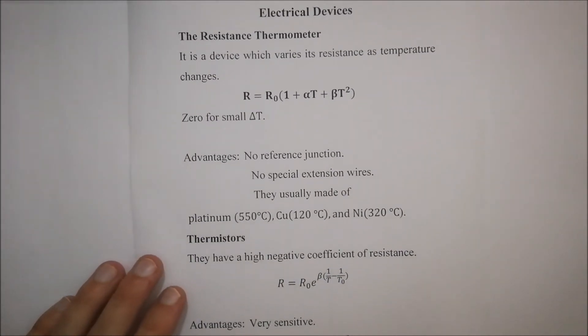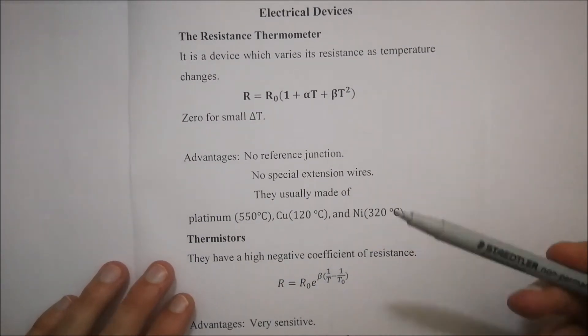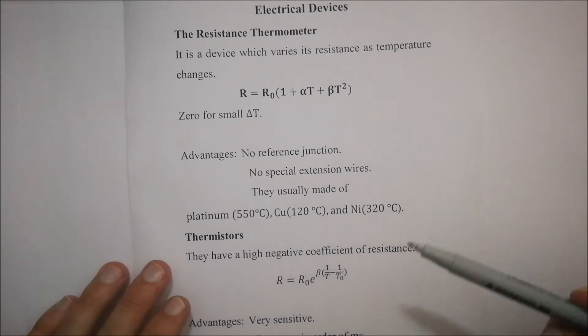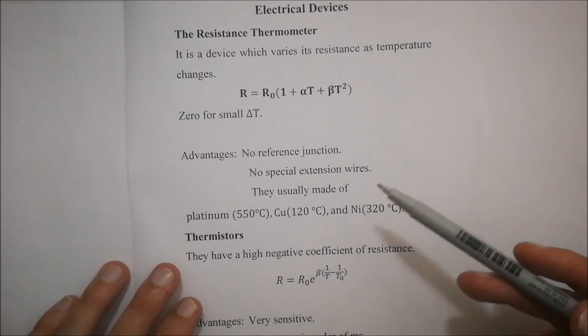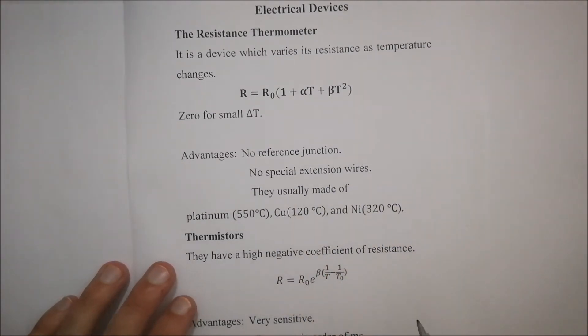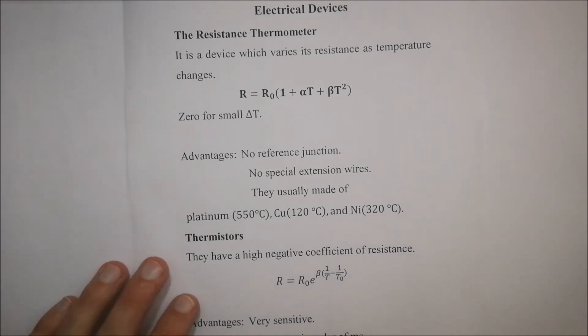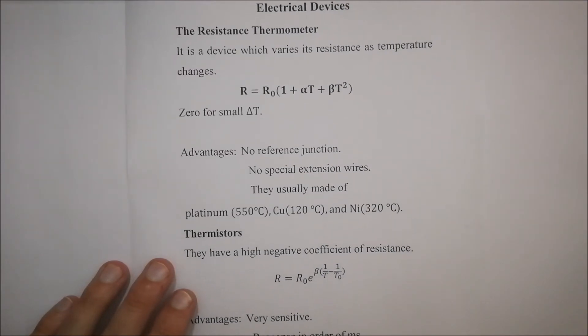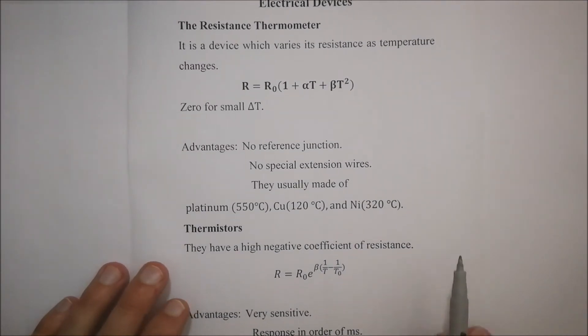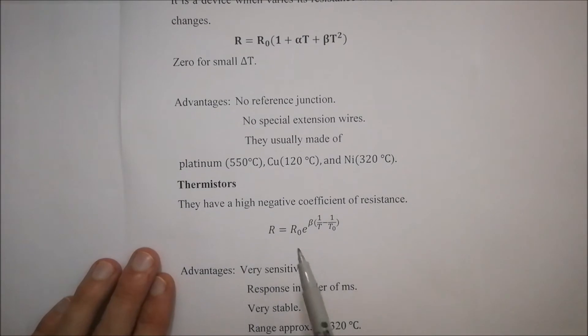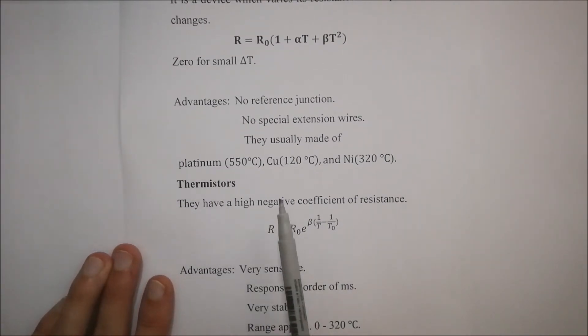The advantages are that there's no reference junction needed, and you'll see where, or at least why this is important. There's no special wires or special extension wires that are needed. You'll see other examples very soon where that is a factor that we need to take into account. And they're usually made of platinum, that's if you want to measure temperatures of about 550 degrees Celsius. Copper for temperature of 120 degrees Celsius, and nickel for temperature of 320 degrees Celsius.